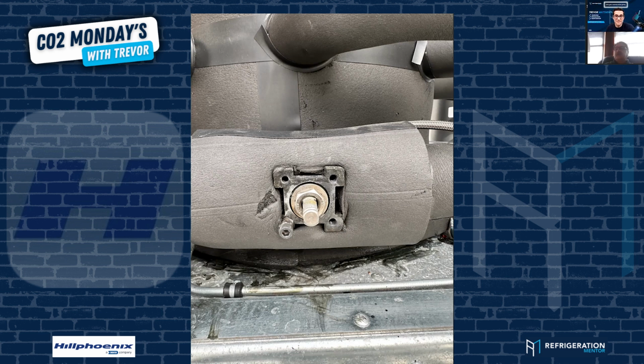Yep. And people start adjusting them, then those settings, they start changing where that algorithm's working. And the next thing you know, they came back to us, they had 2 racks. They said the compressors were undersized. Well, I pulled the programs, I corrected the issues with the iPro programming, had them put the valve back to 100%, because what they were doing is they were producing probably 50 to 60% liquid, and the rest was all gas that had to be consumed by the compressors. And then all of a sudden you're dumping more gas than needs to be dumped, and you become inefficient.